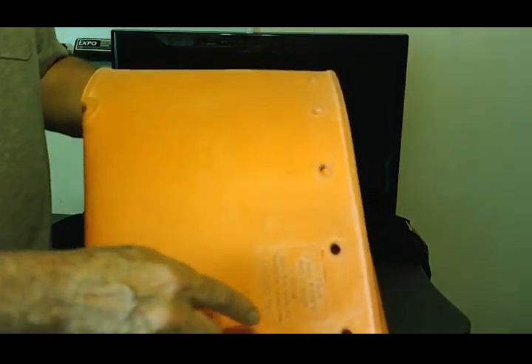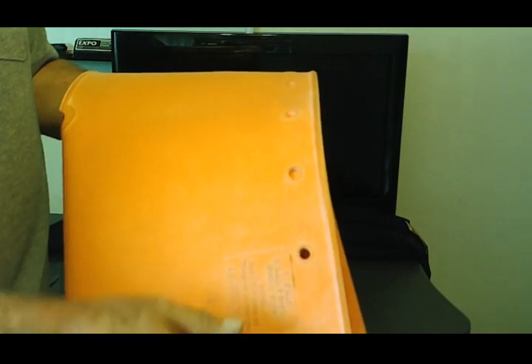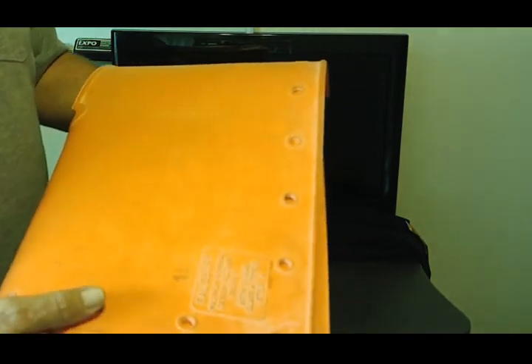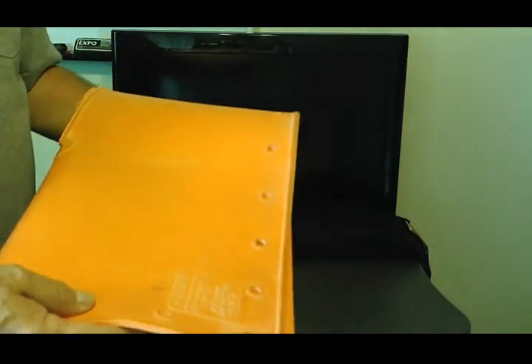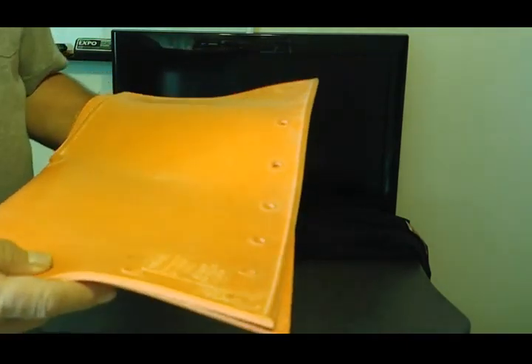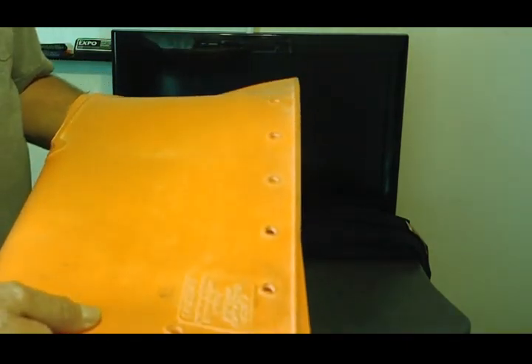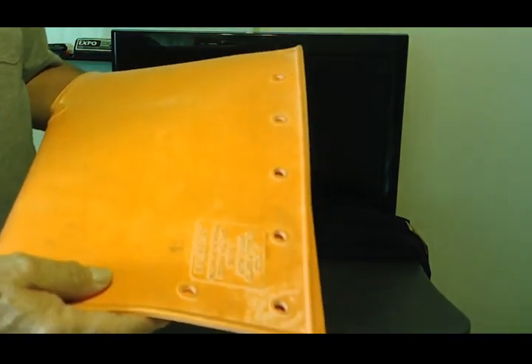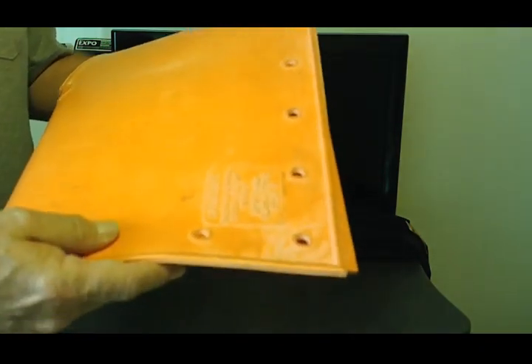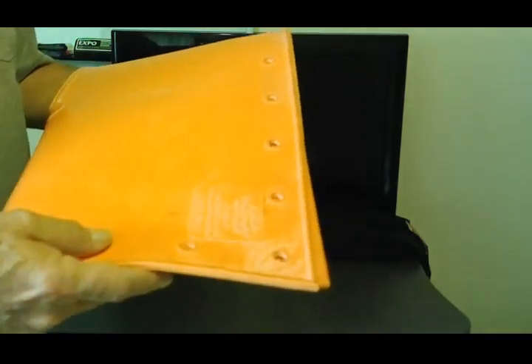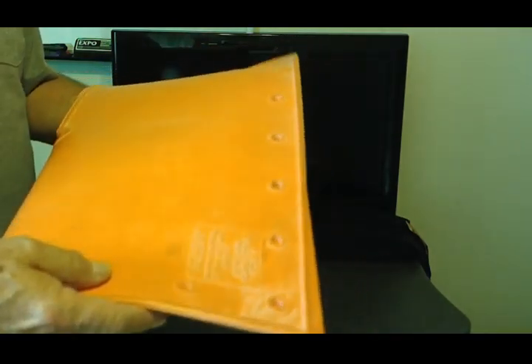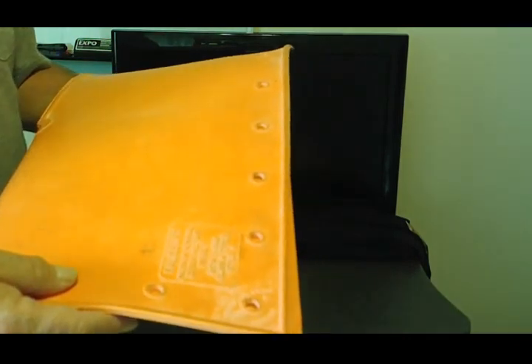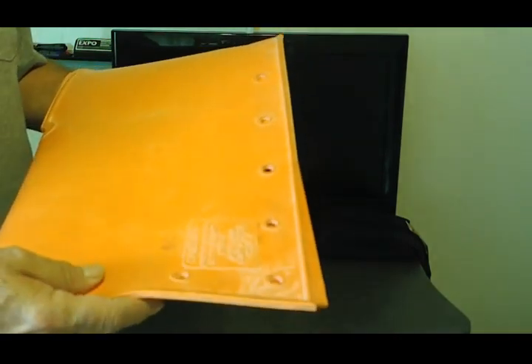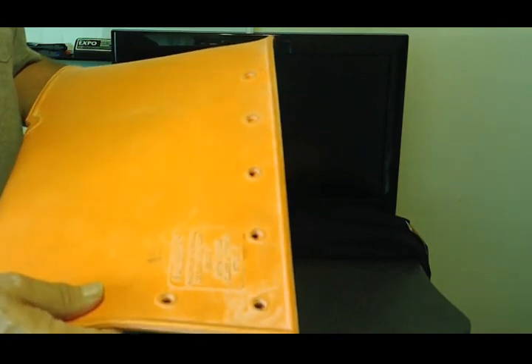Okay, now another point right there is electrical protection. Here we have a rubber blanket. This blanket right here is rated to 36,000 volts. There's blanket materials in all shapes, sizes, and voltage ratings. You can get blanket material anywhere from 1,000 volts up to 36 kilovolts. This is what you use to cover live parts, cover up equipment that's being worked on, and protect the workers from shock. So there's all kinds of blanket materials, and it should be made available. You should probably have some type of it in your facilities.